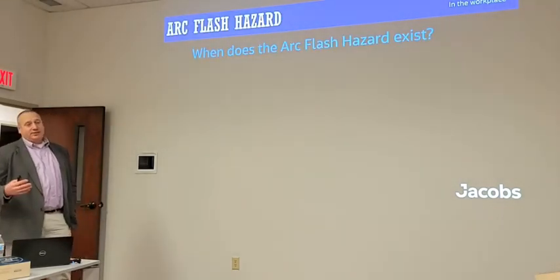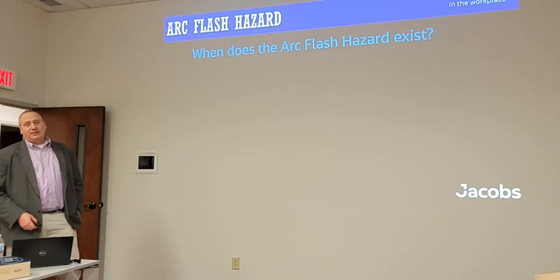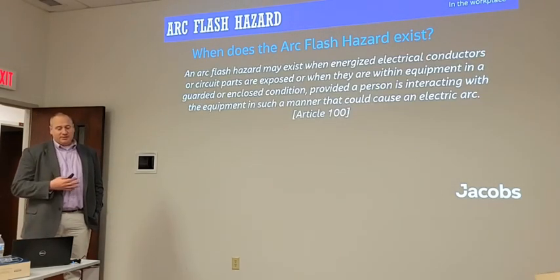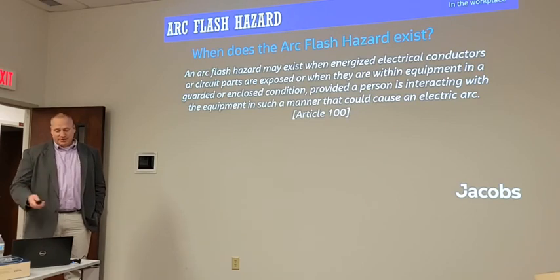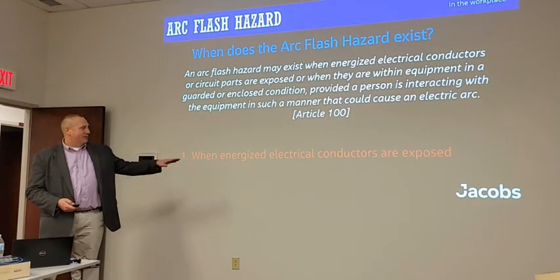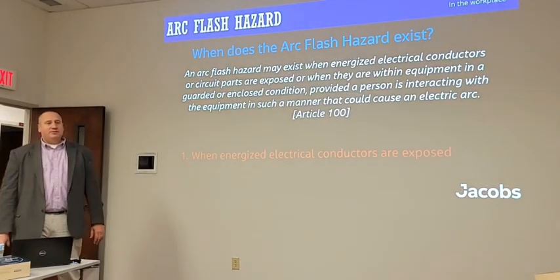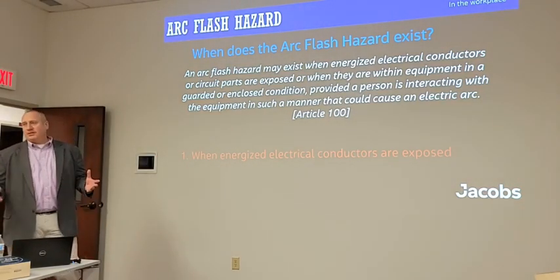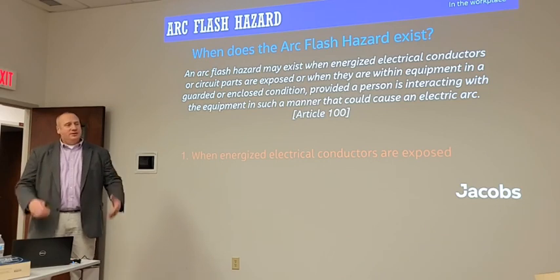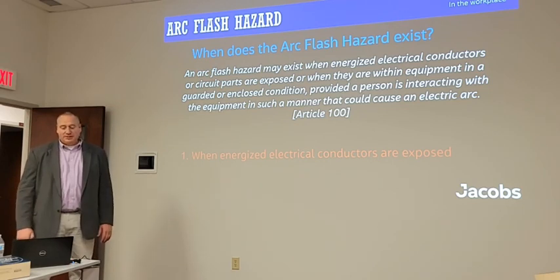So then the question is, when does the arc flash exist? Well, NFPA 70E gives us this definition, and I'll spare you that. You can read it if you want, but I'll boil it down to two scenarios. One, the obvious one, is when energized electric conductors are exposed, you have a potential arc flash hazard. If your conductors are out there where you can make contact with them, obviously that's a hazard.